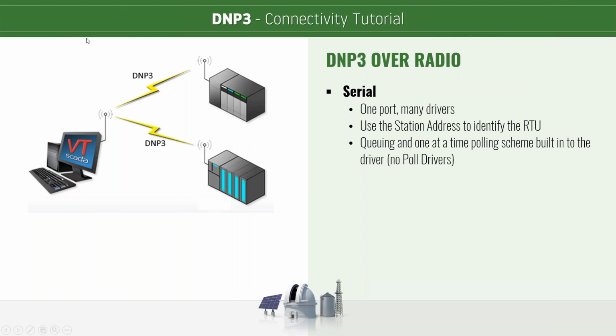So two different flavors of radio that we'll talk about. Serial radio, you're going to have one port and you're going to have many drivers. So you're going to have one serial port tag inside VTScada. You're going to have all of your DNP3 drivers using that port. Maybe as children would be a good way to do that.